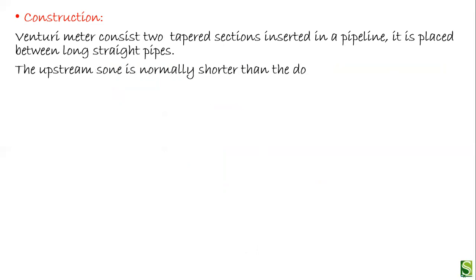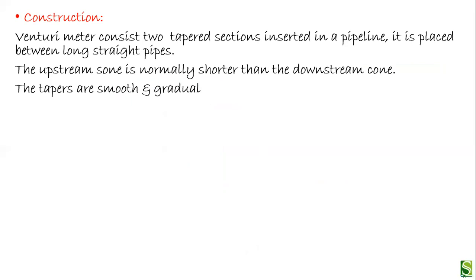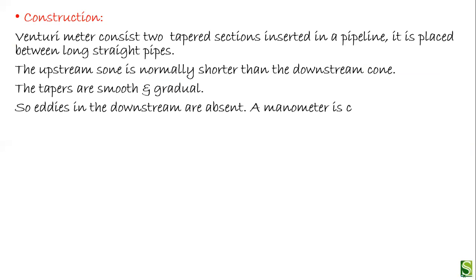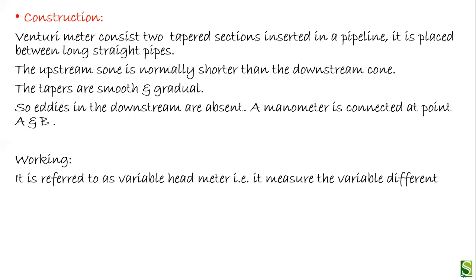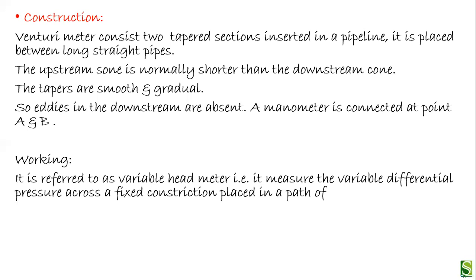The venturi meter is placed between long straight pipes. The upstream cone is normally shorter than the downstream cone. The tapers are smooth and gradual, and in the downstream section eddies are absent, so there are no sudden changes in the flow. A manometer is connected at points A and B. It works on the same principle as the orifice meter — it is also a variable head meter that measures the variable differential pressure across a fixed constriction placed in the path of flow.